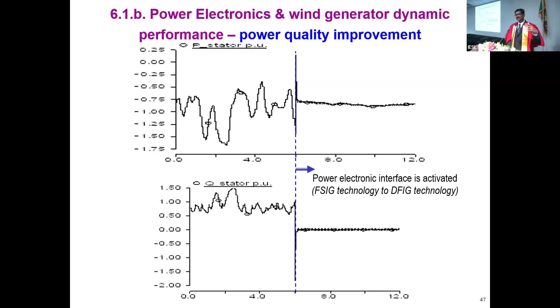In this plant, if you wanted to improve the power quality, basically the double fed wind generator, you know the torque speed curves. That will be shifting this way and that way. Early days we don't shift it because the induction generator resistance and inductance are fixed. Nowadays we open the induction generator rotor winding and inject the voltage, varying the resistor and inductor so that the torque slip curve will shift up and down. Whenever we shift, we can avoid any kind of power quality problem. When the torque slip curve shifts, we allow the machine to speed up, or when it shifts the other way, we allow the machine to slow down. By doing that, we are storing the fluctuating power as a flywheel action into the rotor. Tons of mass is rotating in the wind turbine, and there the fluctuating power is stored.